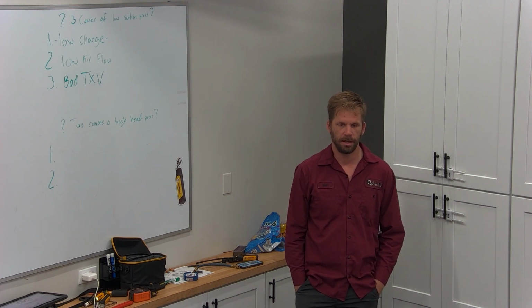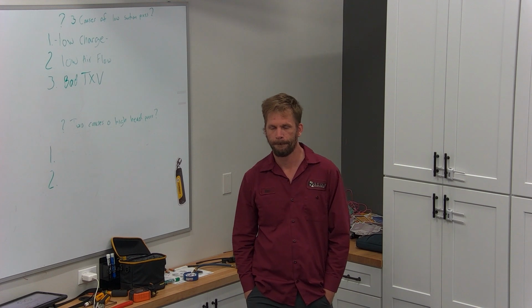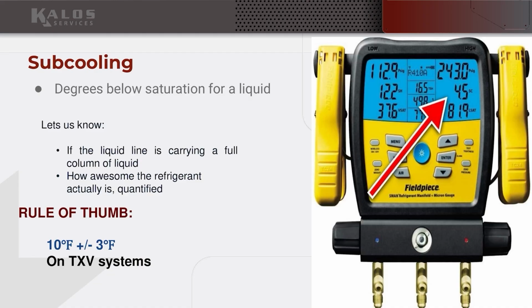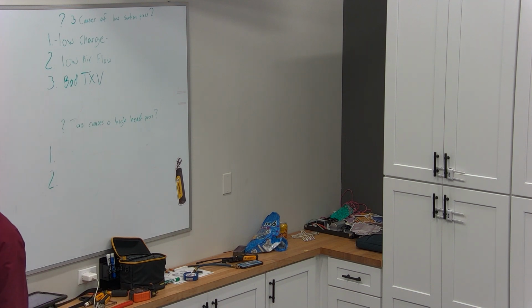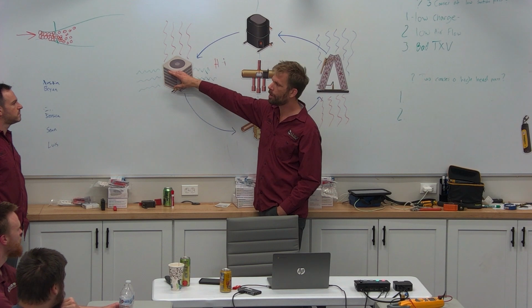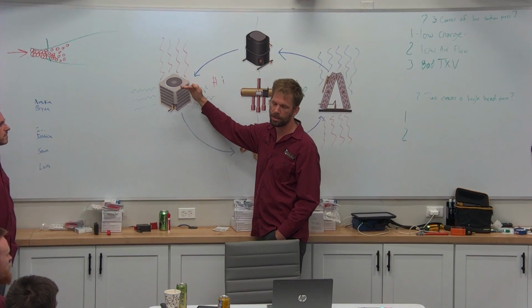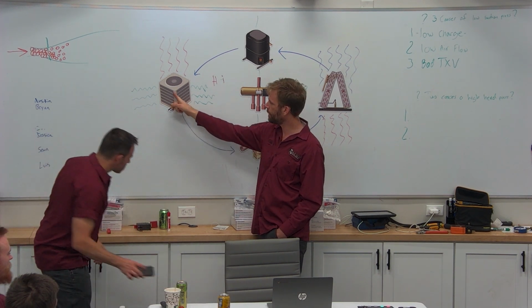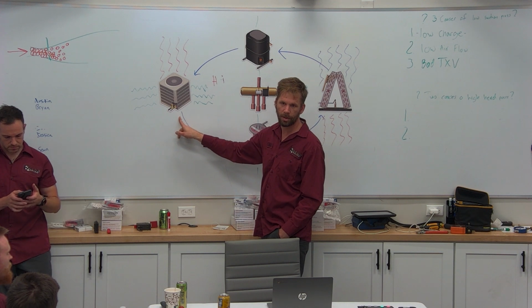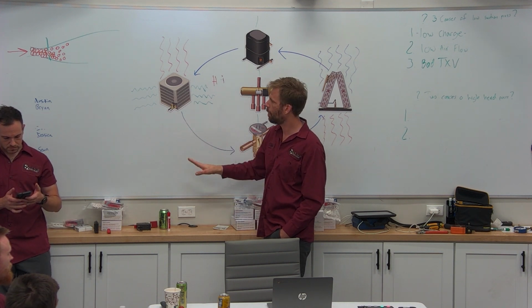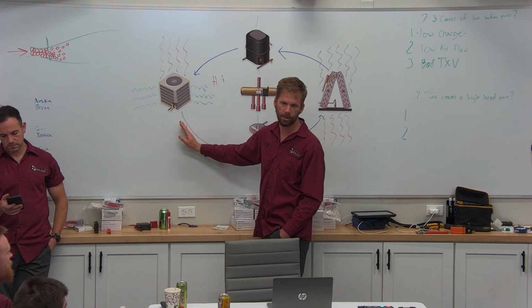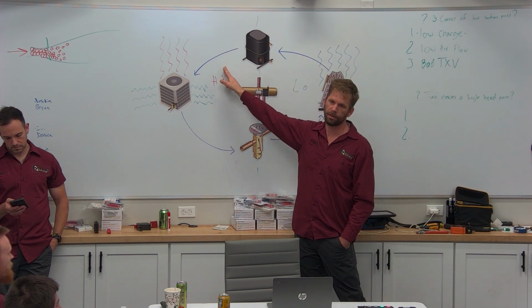But what's the easiest indicator? We just used it on our TXV. Yeah, that's right, subcool. Subcool is the easiest way to prove that we have low charge. If you remember, low subcool means we have a low amount of refrigerant, and good subcool means a high amount of refrigerant. We don't have enough refrigerant to stack up in the coil long enough to come into a liquid and then drop even lower in temperature below the liquid. It's coming out of there sometimes at zero subcool, still partly saturated. All you need to take away from that is low subcool, low refrigerant. If both sides are giving you low refrigerant signals, you're low in refrigerant.